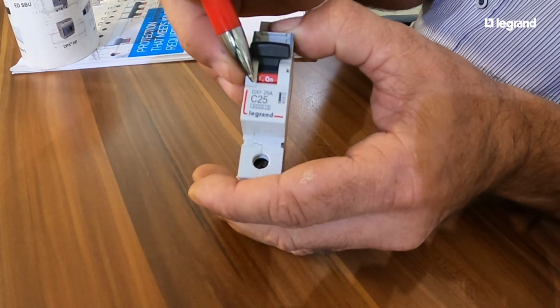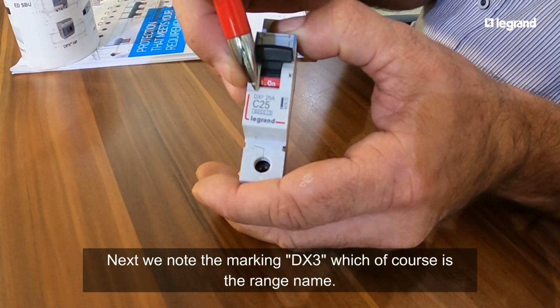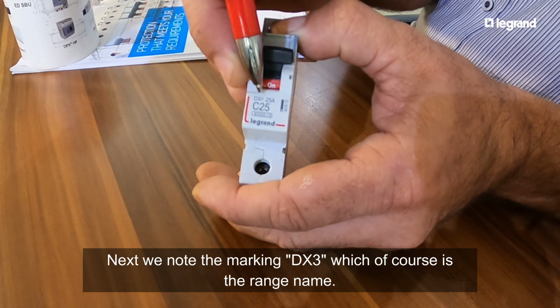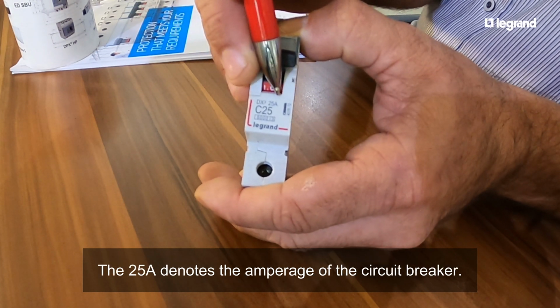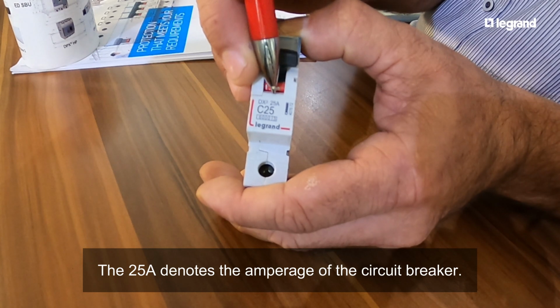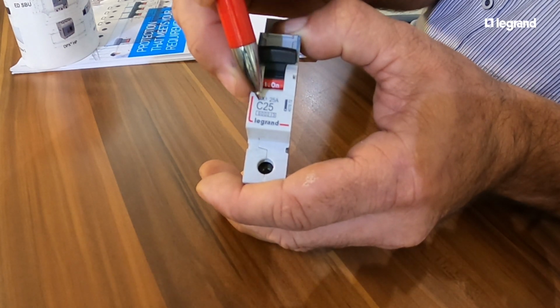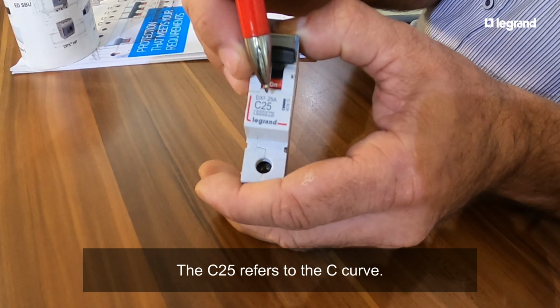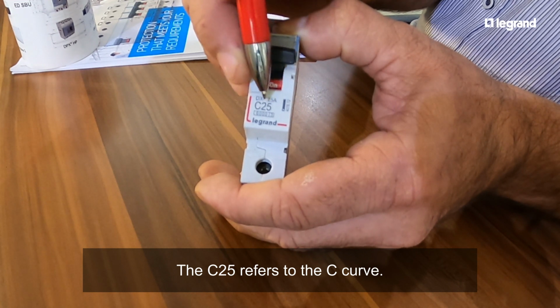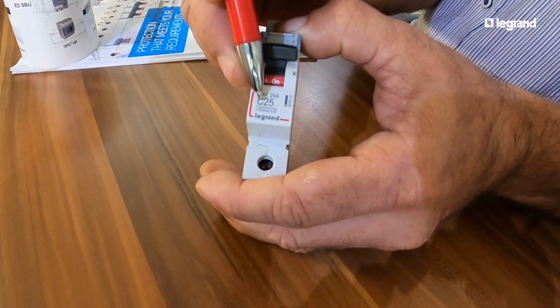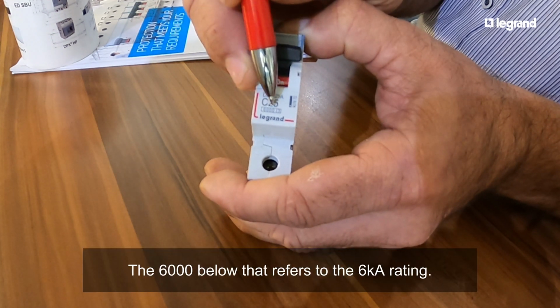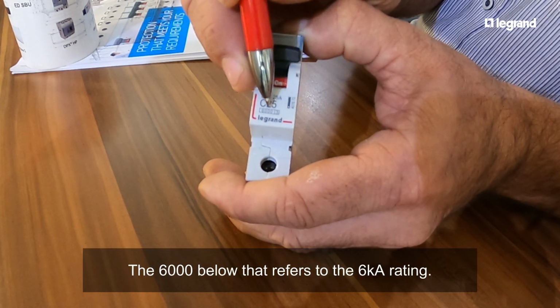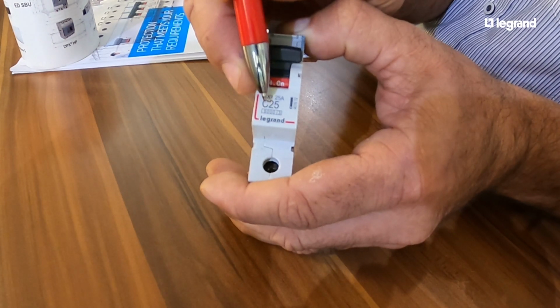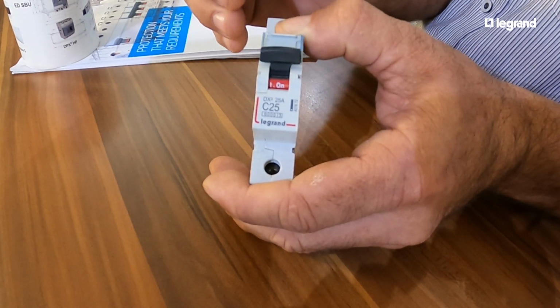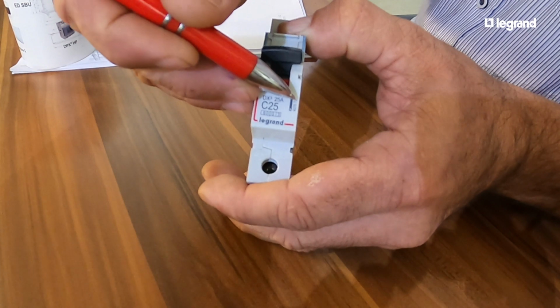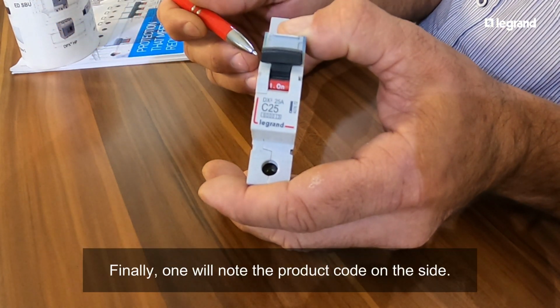Further to this, you will see a marking that says DX3, that's the product class, with a 25A, which gives you the amperage, that's 25 amps. And then the C curve, I'll explain the C curve in a moment, but there it says C25, once again referring to the amperage. Below that there is a 6000, so that 6000 refers to the kA rating of the circuit breaker. In this case, it's a 6kA circuit breaker. And then the part number printed on the side.